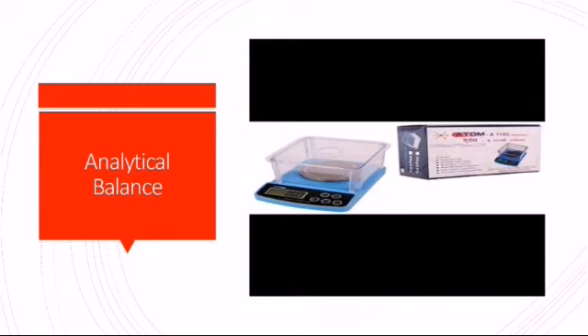Electronic analytical scales measure the force needed to counter the mass being measured rather than using actual masses. As such, they must have calibration adjustments made to compensate for gravitational differences. They use an electromagnet to generate a force to counter the sample being measured and output the result by measuring the force needed to achieve balance. Such a measurement device is called an electromagnetic force restoration sensor.